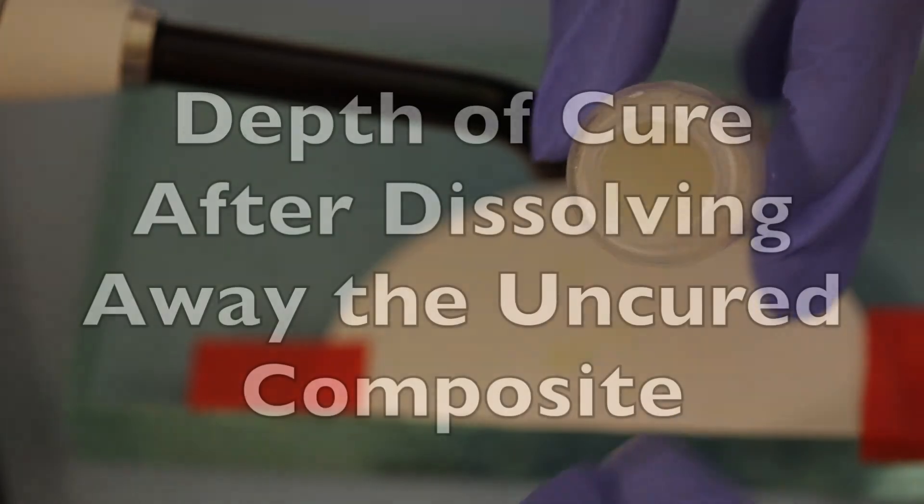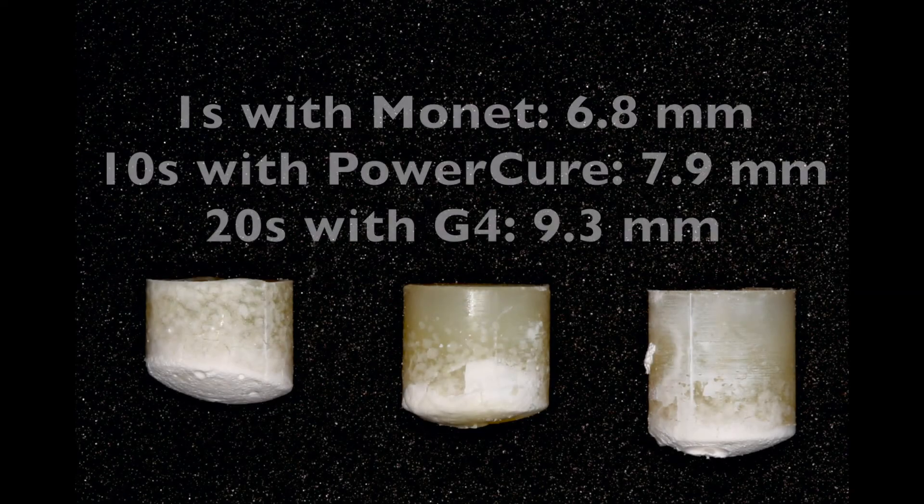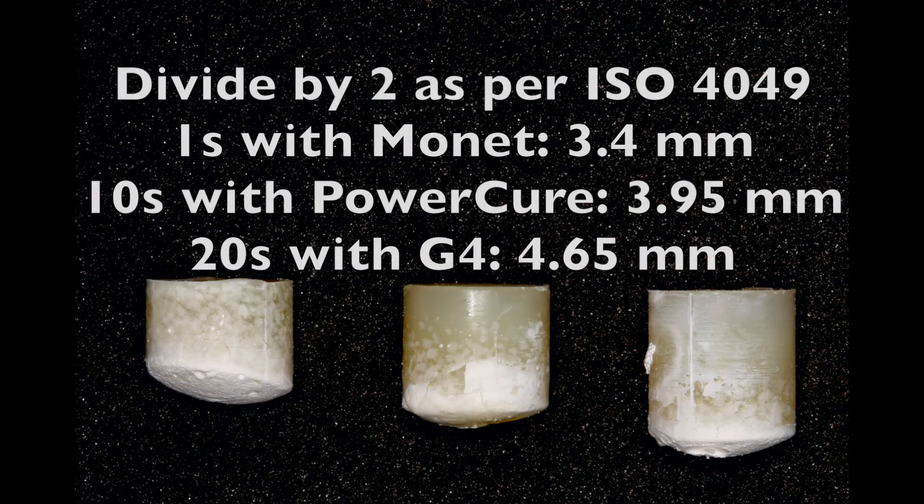Let's look at the depth of cure of those three specimens. 1 second with the Monet: 6.8mm. 10 seconds: 7.9mm. And 20 seconds with the G4 gave you 9.3mm. Now if we divide that number by 2 as per the ISO, the 1 second with the Monet gave 3.4mm, whereas the 20 seconds with the Bluephase G4 gave you the best depth of cure.